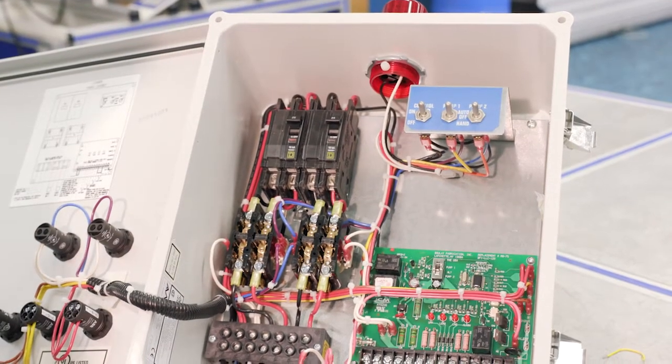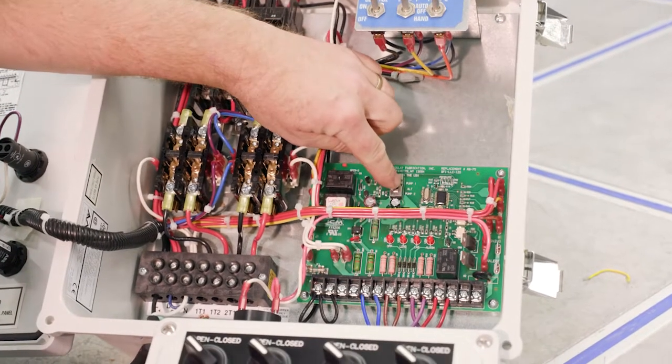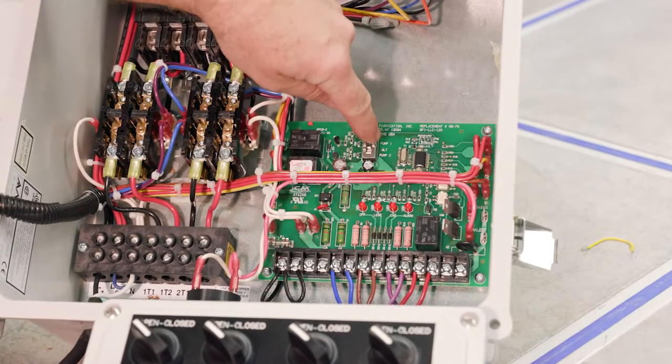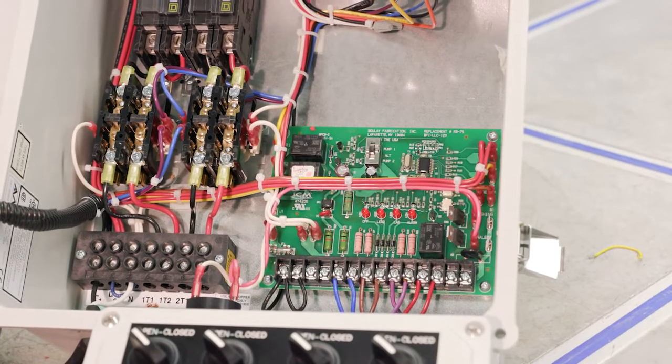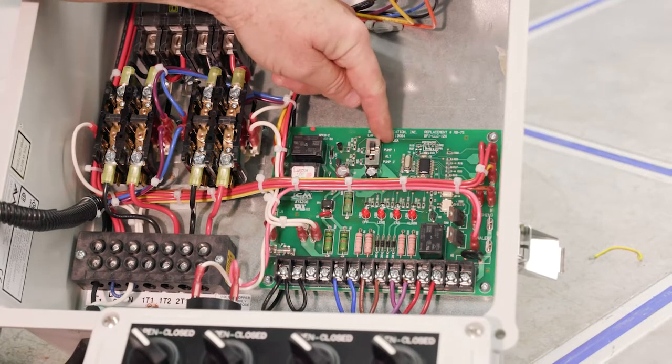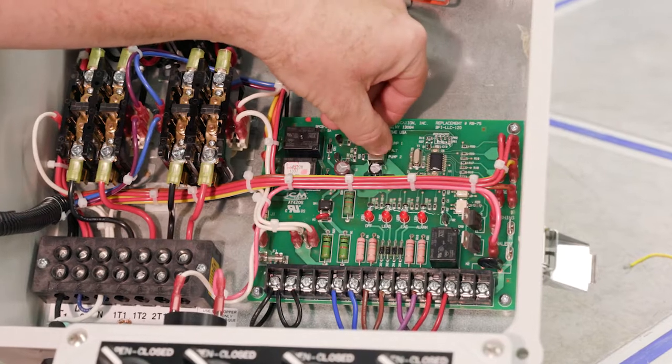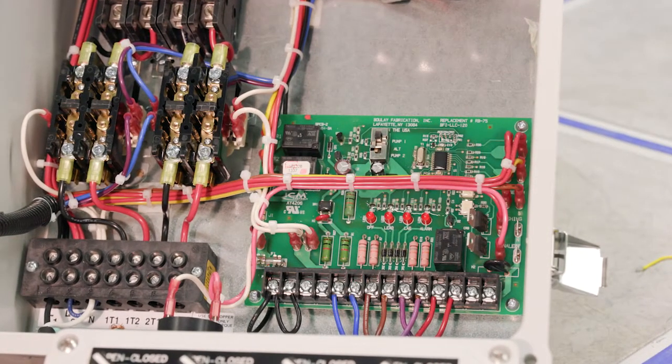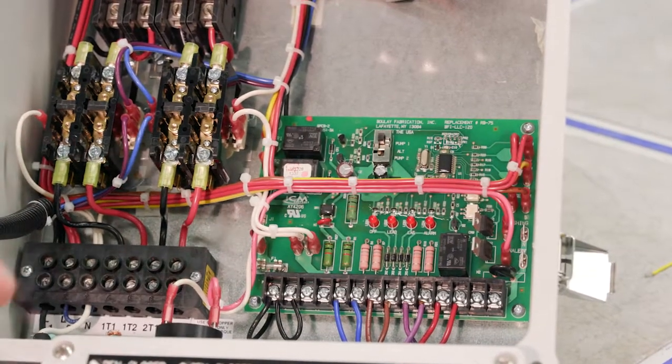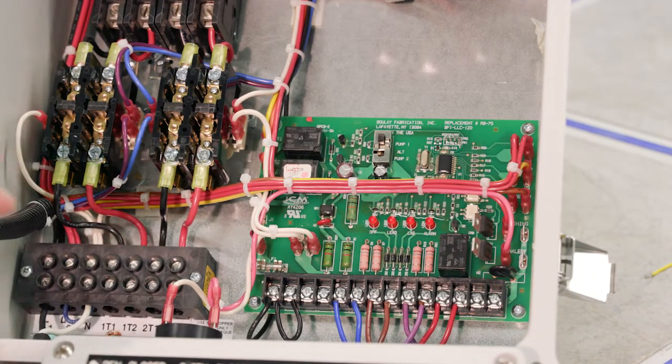The other feature that this box has is the alternator. So in normal applications, we want to leave that switch in the middle which is set to alternate. The two options that you have other than that are move it up to pump one and move it down to pump two. So we'll show you sort of how it works. So let's say that we move it up to pump one. It's basically saying that I've pulled pump two out, and it's out for repair. So I only want this thing to call for pump one.